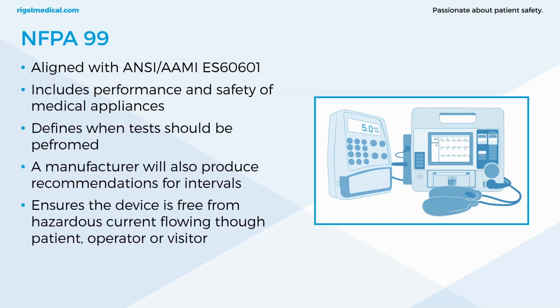So NFPA 99 is aligned with ES 60601. There are a lot of similarities. It's derived from that standard. But NFPA 99 is broad. It's the performance and safety criteria that refers to the healthcare facility in its entirety. It's not only the performance and safety of the equipment itself, it covers everything. So I'll give an example, closely related to electrical safety of the devices, but it's the ground bond and strain relief tests of the receptacles. So that's ensuring that the actual plugs, the extension leads, they have the correct polarity, and it's all part of the same procedure.